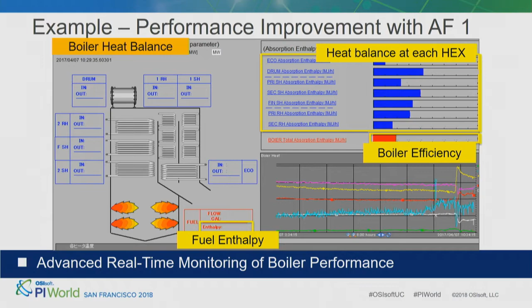So we can identify the cause of decreased boiler efficiency and make a proper inspection plan focusing on a specific part of the boiler. We can also use soot blowers at the proper points and best time to improve boiler efficiency.